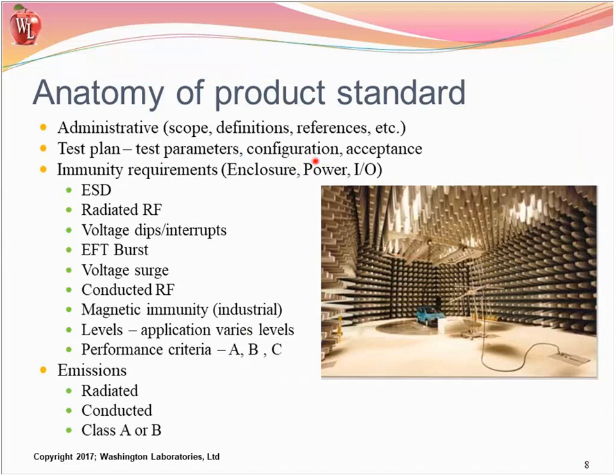So the acceptance criteria deals in the product standard. It normally puts immunity requirements for several kinds of things, and it may or may not be these, and it may be different. But they also include performance requirements. You may or may not have a requirement for magnetic immunity. You may or may not have an ESD requirement if it has some exemptions, etc.